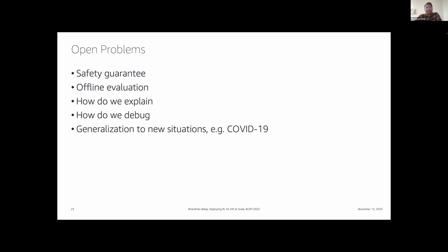That's why I'm raising it here, because we had control over that building and they let us experiment in that building without a lot of guardrails, and that's not going to happen in most real buildings. The most we enforced was the set point, that set points don't cross a given range, and without that, thermal comfort would become really an issue. But how do we do that systematically? No clue. And that's part of the problem.